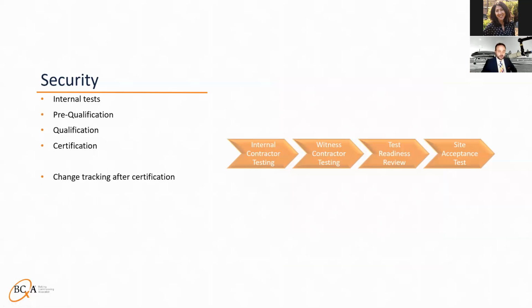Security testing with security contractors or security agencies is a key part. There are internal tests from the vendor, then pre-qualification, where the security agency will send somebody to witness some of the vendor's testing. Then there's qualification tests to make sure the system's ready for a full certification, and certification tests where each security function on each conveyor is verified. So this is bags being removed, bags being added, or sliding out of their tracking windows. Once the agencies have approved the system, there's change tracking that's required, so that any changes to those PLCs must be reported so that the agencies can check them if they choose to.